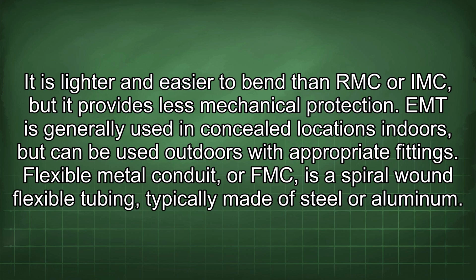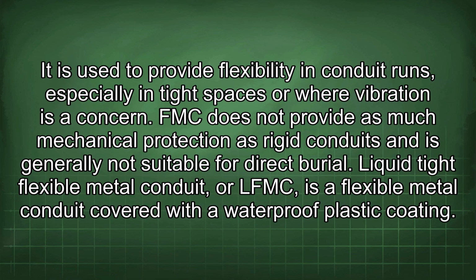Flexible metal conduit, or FMC, is a spiral wound flexible tubing typically made of steel or aluminum. It is used to provide flexibility in conduit runs, especially in tight spaces or where vibration is a concern. FMC does not provide as much mechanical protection as rigid conduits and is generally not suitable for direct burial.